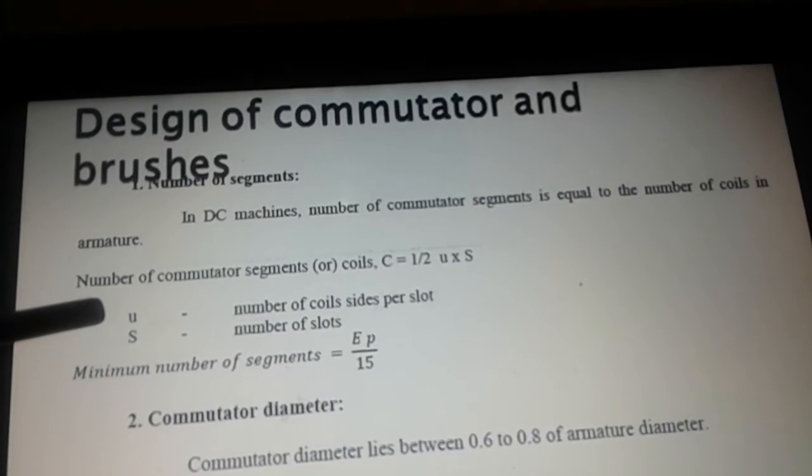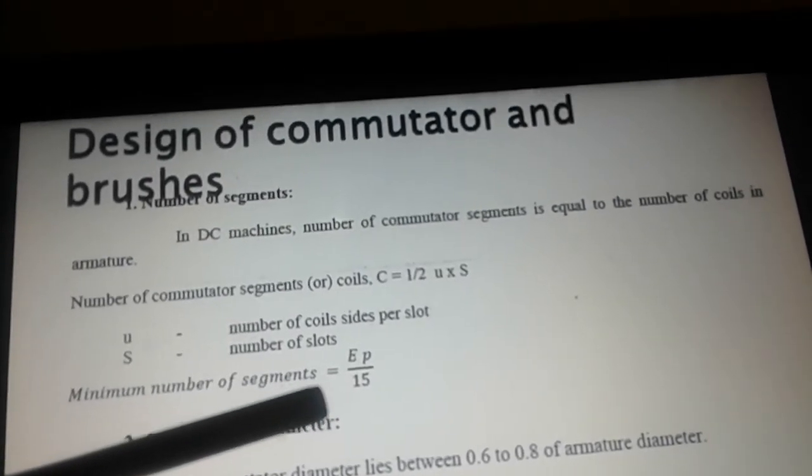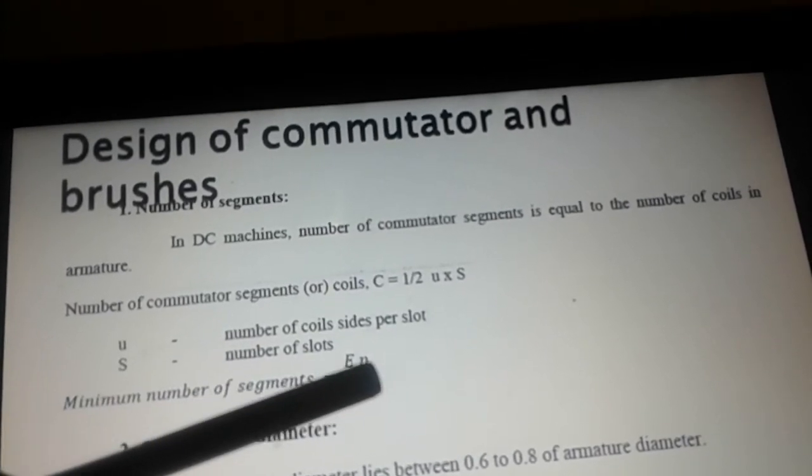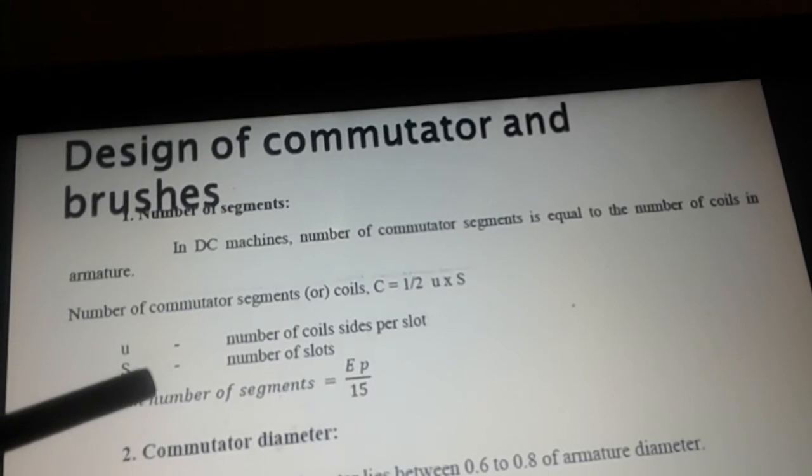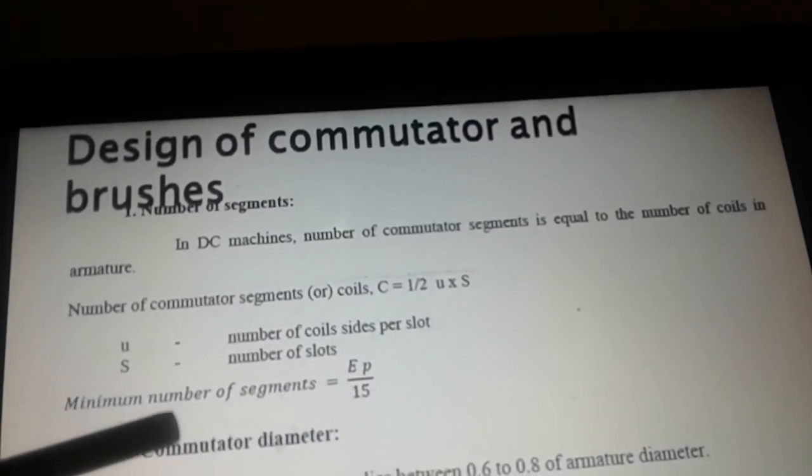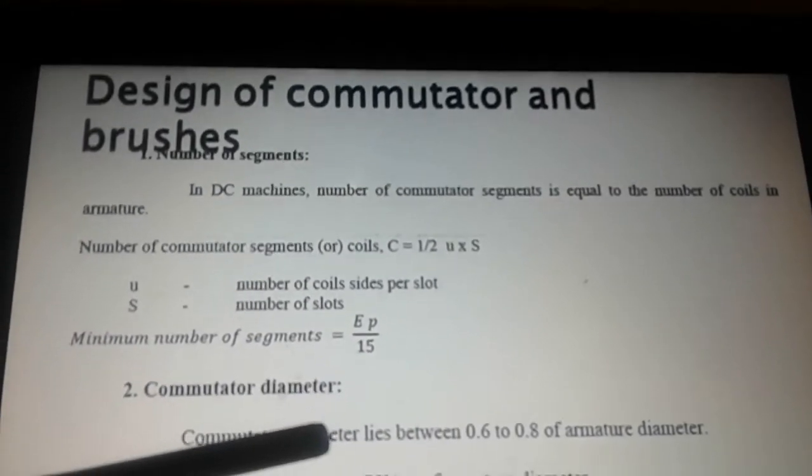So the number of coils or number of commutator segments is equal to half US, where U is the number of coil sides per slot and S is the number of slots. The minimum number of commutator segments is EP divided by 15.